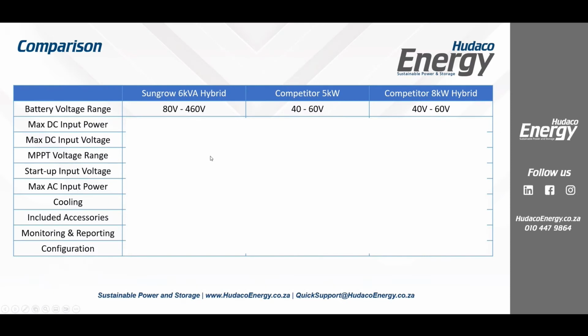Just a quick comparison. You asked what some of the differences are between our system and a more common competitor at 5 kilowatt and 8 kilowatt hybrid. The first thing is the voltage. A lot of the other guys, even though they might call it a high voltage system, it's actually not. It's higher than 48, but it's not high voltage. In our case, we use up to 460 volts, let's call it 500 volts, on the battery side. The advantage here is we can use a 6mm cable. We don't have to buy 25mm cables, or that huge, massive DC box in the middle, about $8,000 once you put all the protection in, with the big cables and ugly big trunking and all the rest of it.